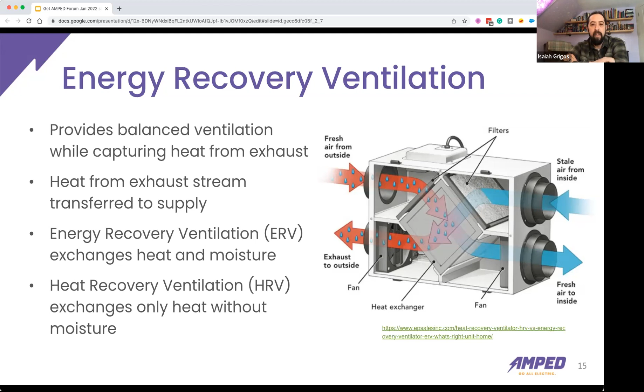Essentially what it does is pull heat from the exhaust air and transfer it into the incoming air, and we're seeing these used in conjunction with heat pumps. You might have a large ERV on a roof, and in the middle of winter, the incoming air pulls heat from the exhaust air, but it's never 100% efficient. So you might be bringing in 50-degree air into living spaces, which you don't necessarily want. In the past, people added a fairly inefficient furnace, but more and more we're seeing them use a heat pump to condition the makeup air for this ventilation, so people don't have 50-degree air blowing on them. Combining energy recovery with a heat pump is the way to go to introduce fresh air in a balanced and efficient manner.